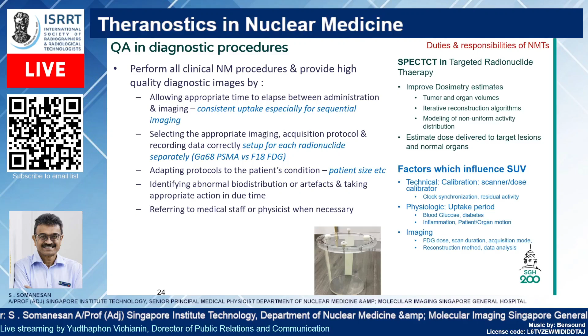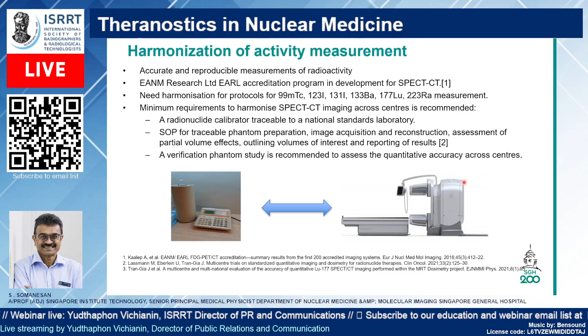Now, the harmonization of activity measurement, we spoke a little bit about this in the last slide. In essence, the well counter calibration, where the dose calibrator is calibrated with the PET scanner, and this needs to be done every 3 months minimum, after every preventive maintenance, so as to make sure that the SUVs are accurate. Every manufacturer of the PET-CT scanner has their own phantom, and that needs to be performed by the physicist or the technologist regularly.